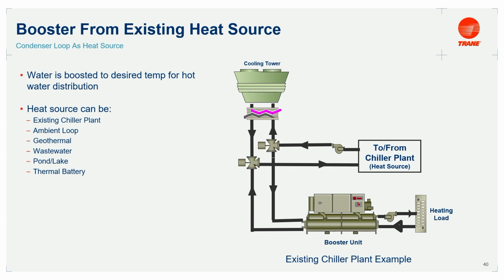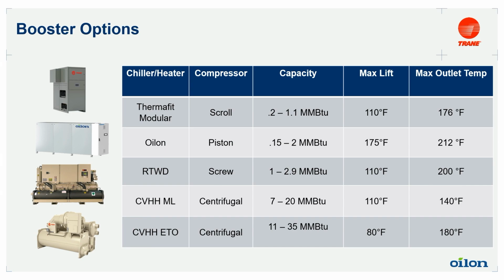So what we're really talking about is, with an existing chiller plant, how do we capture the heat off of that? Maybe an existing chiller can get 95, maybe 110 out of it. If we put that leaving water temperature from the condenser into the evaporator of another chiller heater — a booster, whatever you want to call it — we can drive that up another standard set of lift to get our usable hot water temperature.